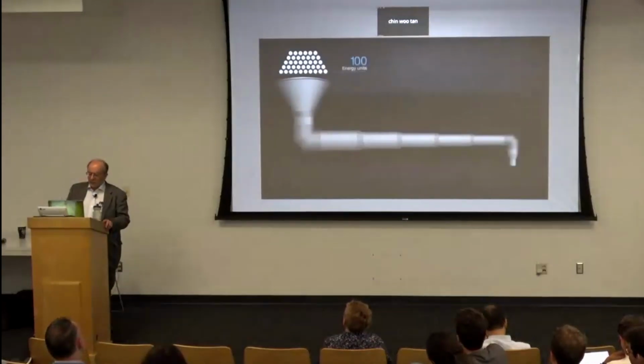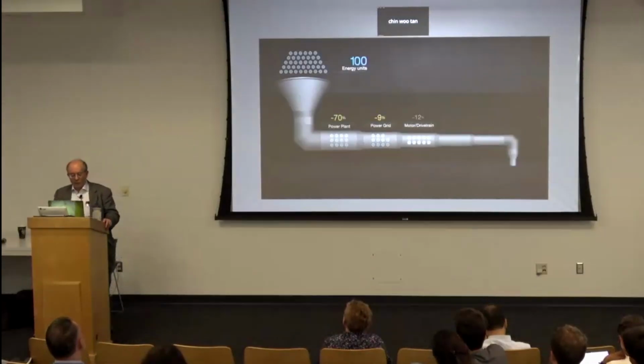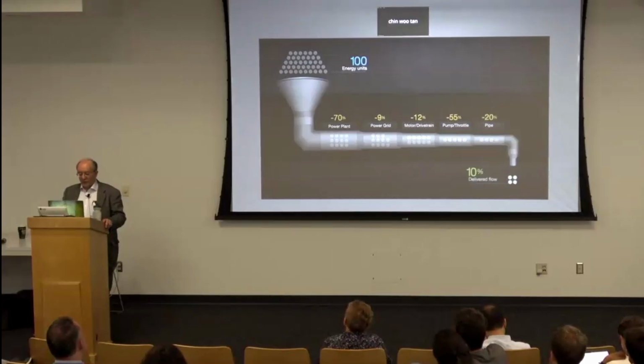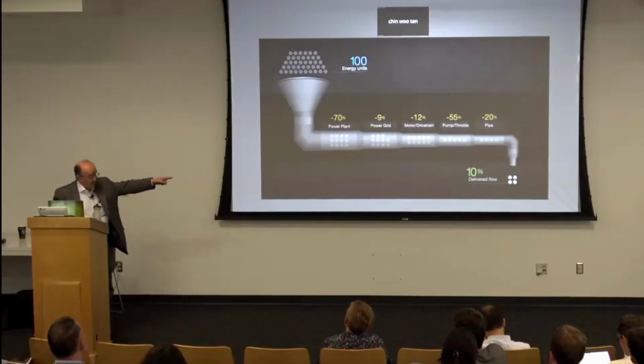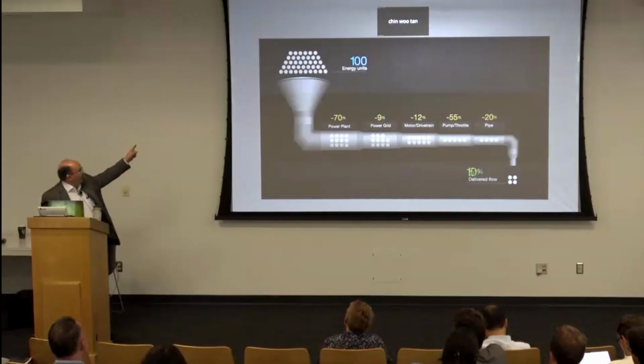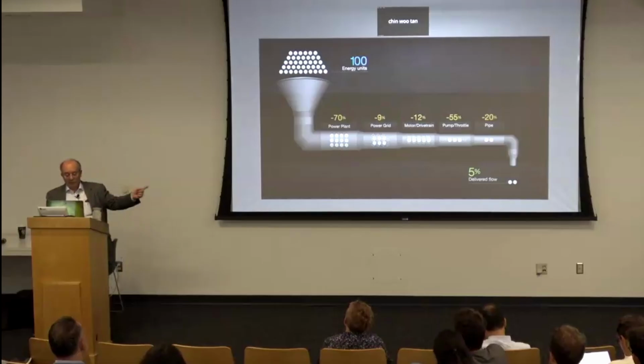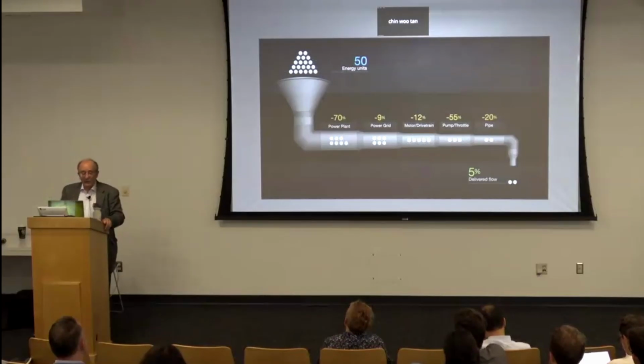What do such savings mean for the pumps and fans that use over a quarter of the world's electricity? From the fuel burnt at the power plant to the end use, many successive losses compound, so only a tenth of the energy in the fuel comes out the pipe as flow. But now turn those compounding losses around, backward from right to left, and they become compounding savings. So every unit of flow or friction you save in the pipe saves 10 units of fuel costs, emissions, and what Hunter Lovins calls global weirding back at the power plant.